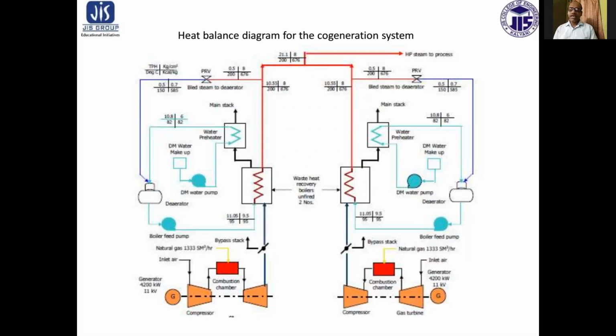So first of all, air inlet from the compressor and through the combustion chamber, it is flowing over the gas turbine. Then the flue gas is moving to the waste heat recovery boiler, and the steam is generated and it is sent to the HP steam for the process. And while the flue gas is passing through the water preheaters, and ultimately it is going to the main stack.